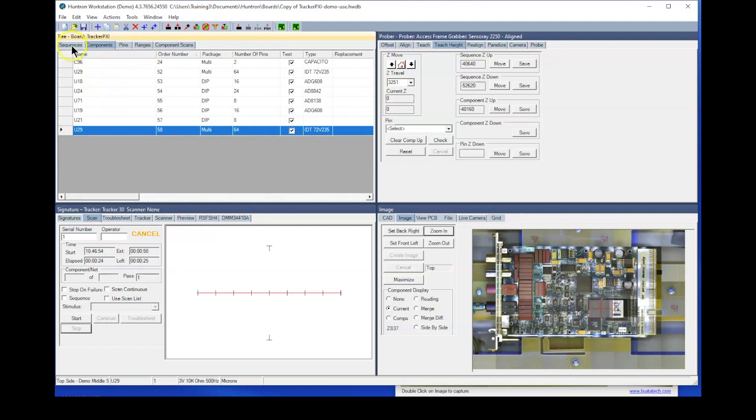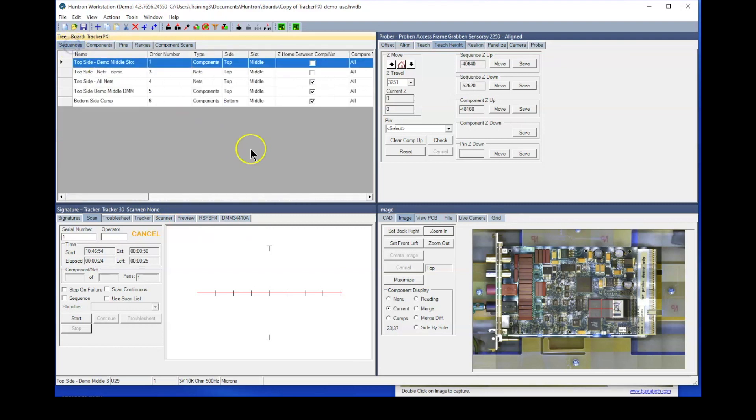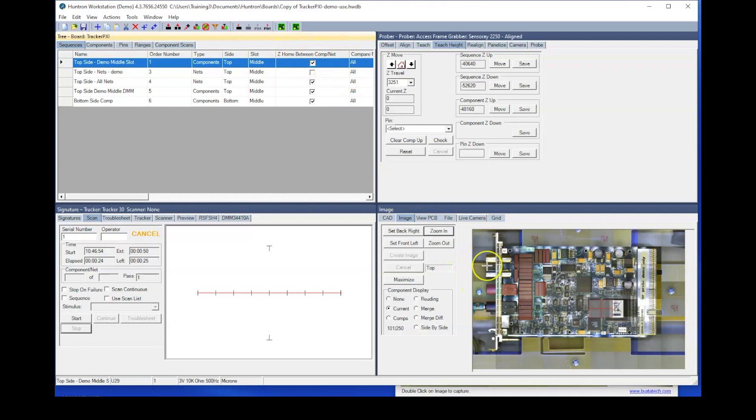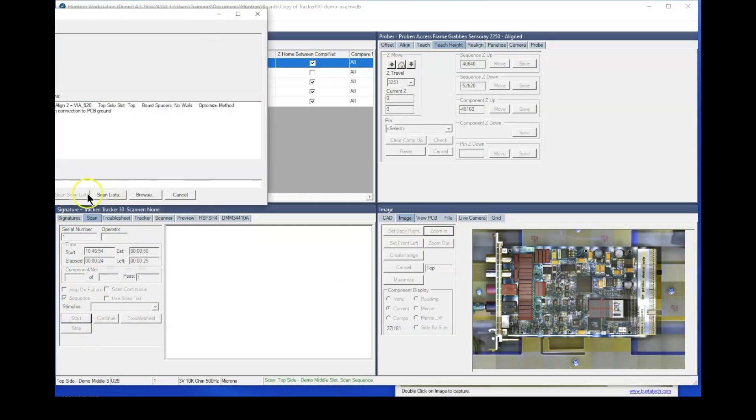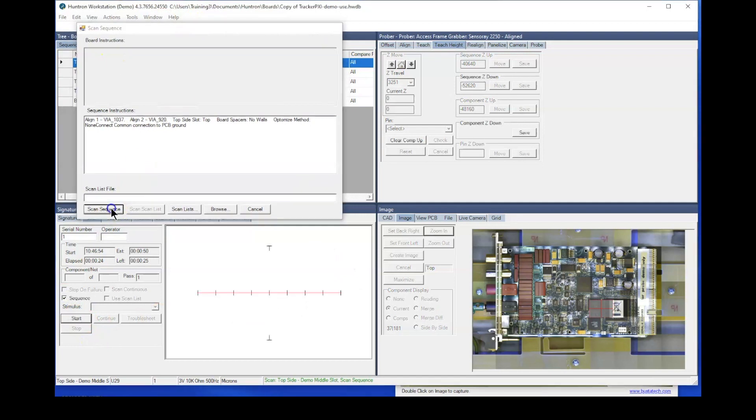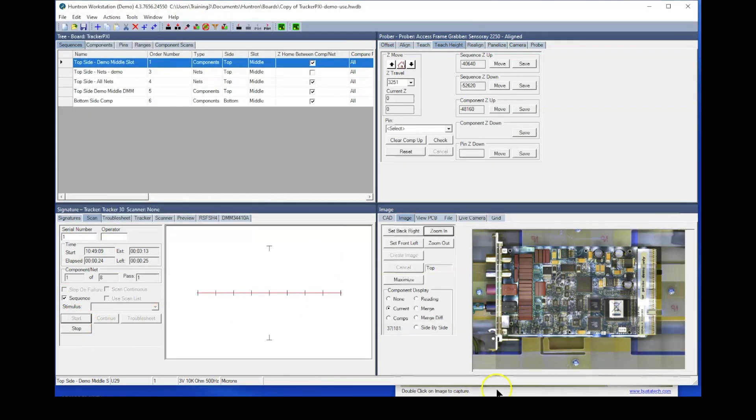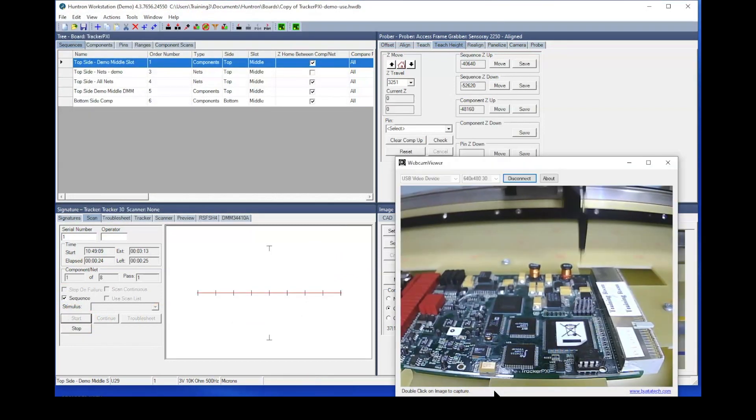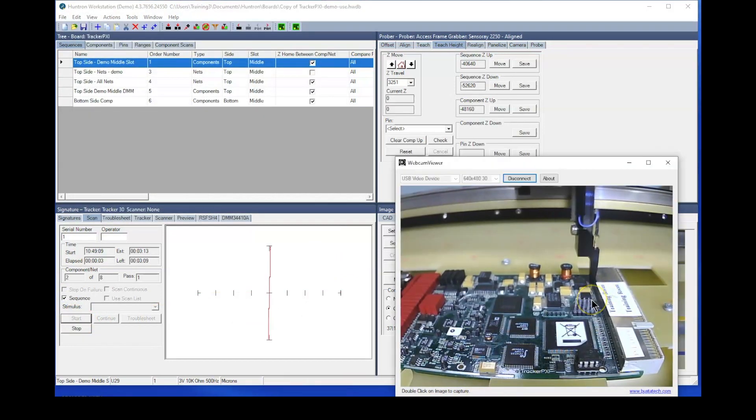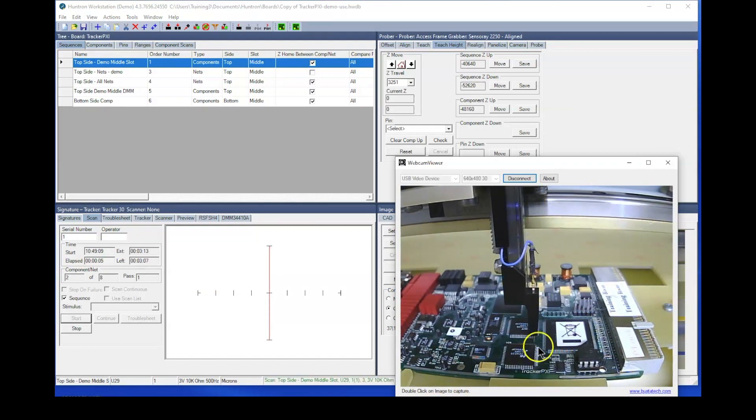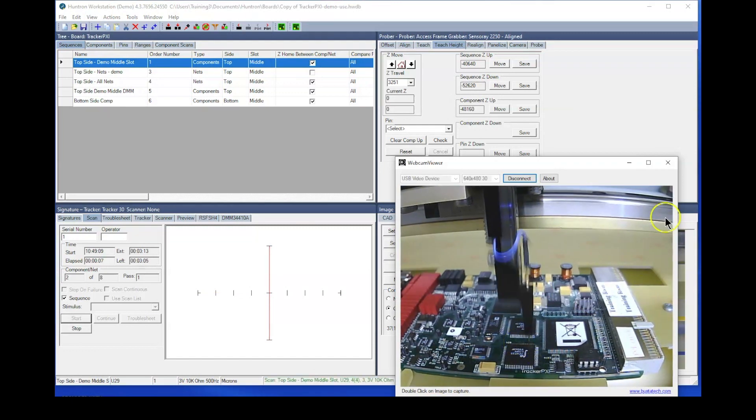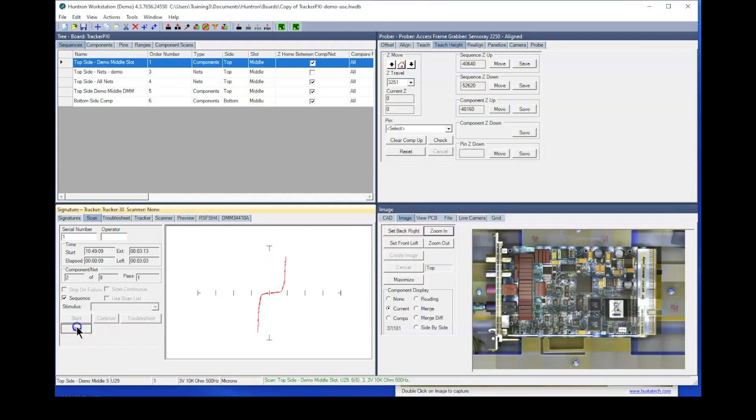One other thing you can do here is at the sequence level. And when you scan a sequence, by default, we have the Z home between components turned on. That means that when it moves from one component to the next, the probe goes all the way home. So let me illustrate that for you. We'll start a sequence scan here. Start and scan sequence, turn the camera on. It'll go up and probe the component here in the back, go all the way home, and then start probing the next component.